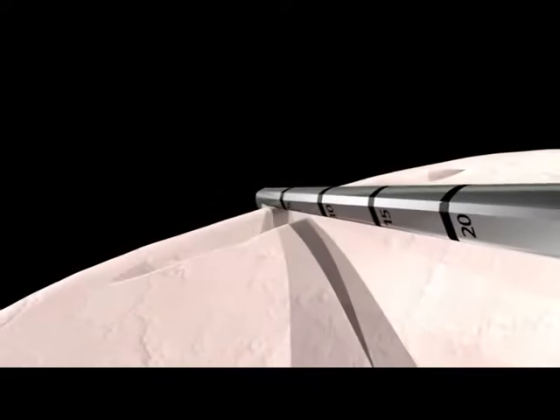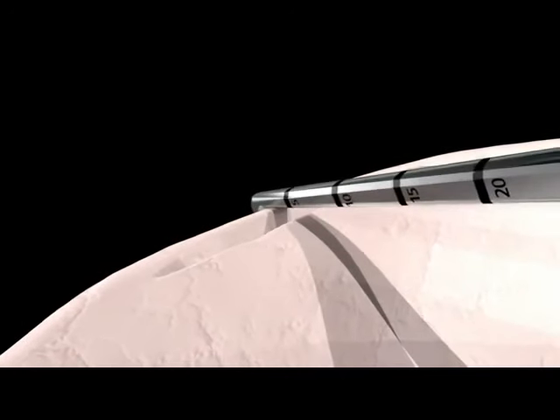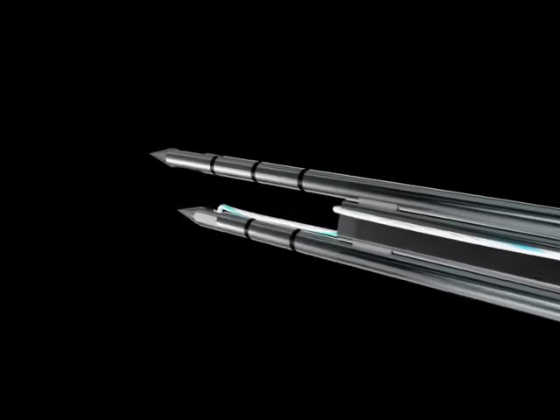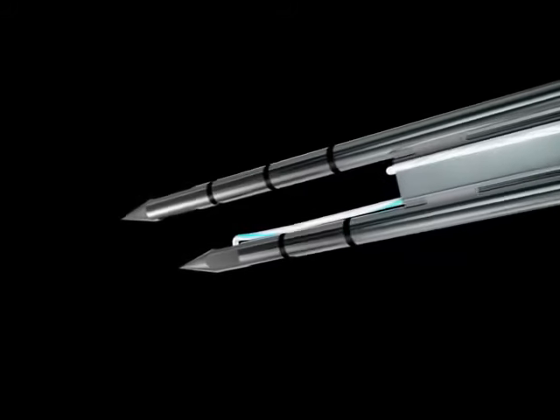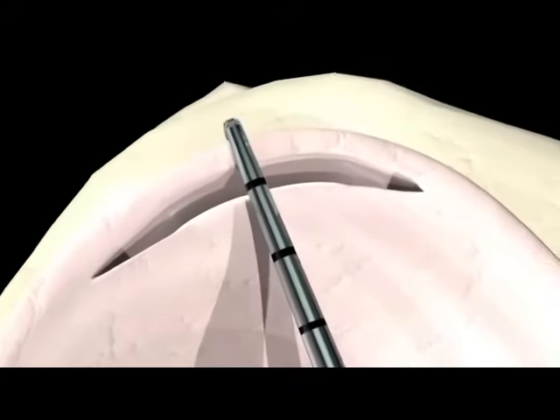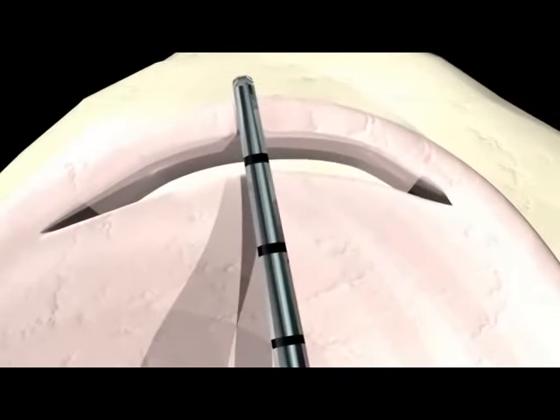Depth laser markings on the probe are indicated at 5 mm increments, as are the depth markings found on the needles of the AS meniscal repair device. Record the intended depth of penetration at the repair site. This will serve as an indicator for how far to advance the AS meniscal repair device and help gauge proper penetration of the tissue.